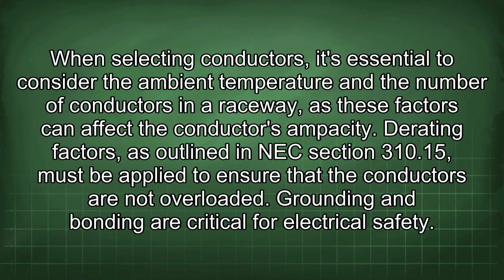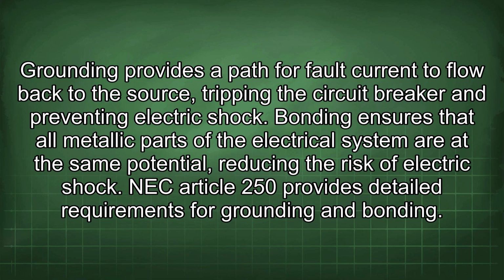Grounding and bonding are critical for electrical safety. Grounding provides a path for fault current to flow back to the source, tripping the circuit breaker and preventing electric shock. Bonding ensures that all metallic parts of the electrical system are at the same potential, reducing the risk of electric shock. NEC Article 250 provides detailed requirements for grounding and bonding.